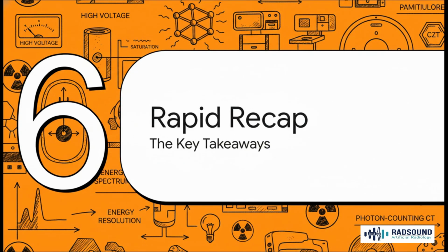Okay, let's nail this down with a super fast 60-second recap. Ready? Go. There are three fundamental mechanisms: ionization in gas, scintillation in crystals, and ionization in semiconductors. Gas detectors are all about the voltage. The stable saturation region is for ionization chambers, perfect for precise dosimetry. The super high voltage region is for Geiger-Müller tubes, great for finding contamination but with no energy info. Scintillators turn radiation into light. NaI(Tl) is the workhorse for gamma cameras, while the blindingly fast LSO enables time-of-flight PET. And finally, semiconductors have the best energy resolution, which is the secret sauce behind photon-counting CT using CZT detectors. The most important thing? Always match the right tool to the right job.